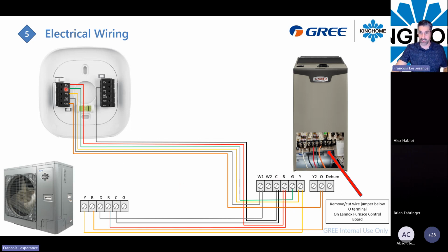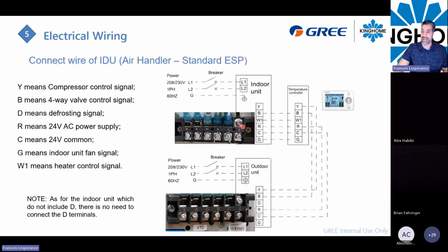So the G from the thermostat will go directly to the G on the furnace, just for your call for ventilation and all the stuff. You will use your Y1 terminal hooked on Y1 for your furnace, and then it goes back to the outdoor unit. But on the terminal strip of an air handler, there is no Y terminal, okay? So you will just have to make a connection with a Marette or something like that. The air handler doesn't have the Y terminal hooked on it.